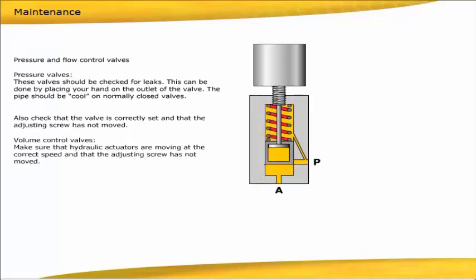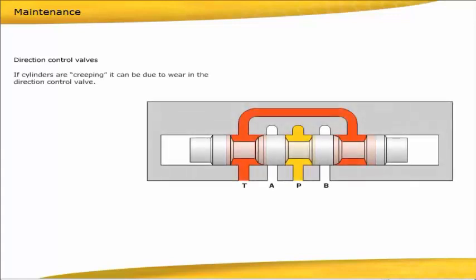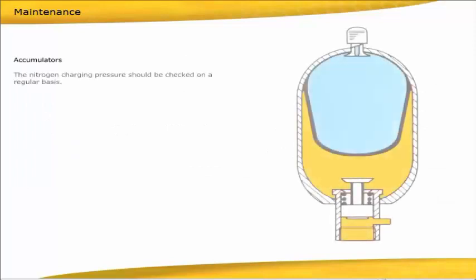Volume control valves: Make sure that hydraulic actuators are moving at the correct speed and that the adjusting screw has not moved. Direction control valves: If cylinders are creeping, it can be due to wear in the direction control valve. Accumulators: The nitrogen charging pressure should be checked on a regular basis. Always use nitrogen when charging accumulators.